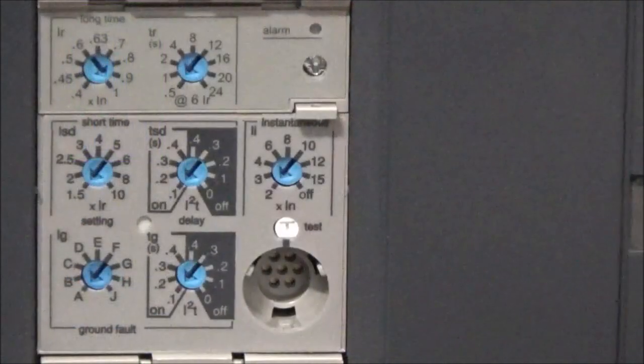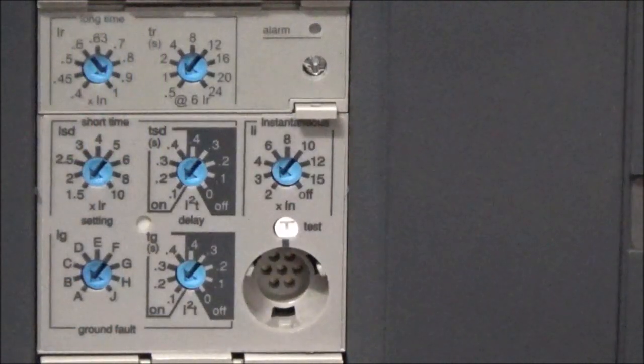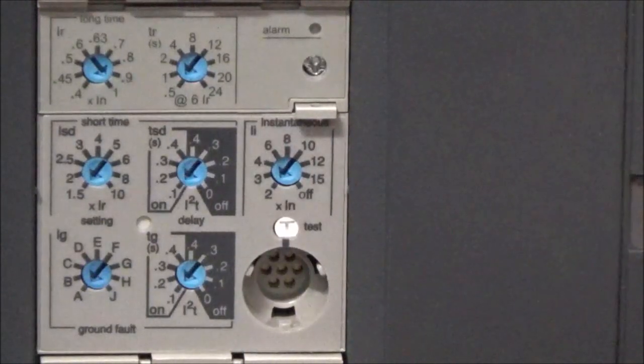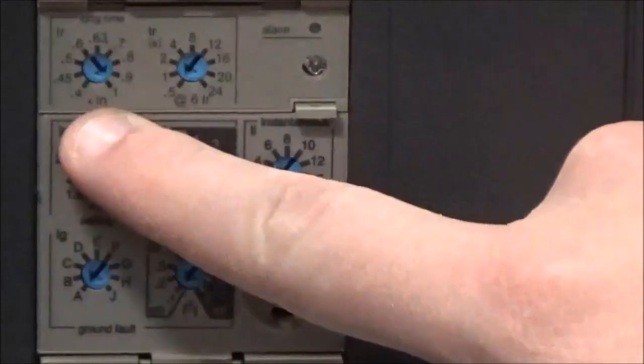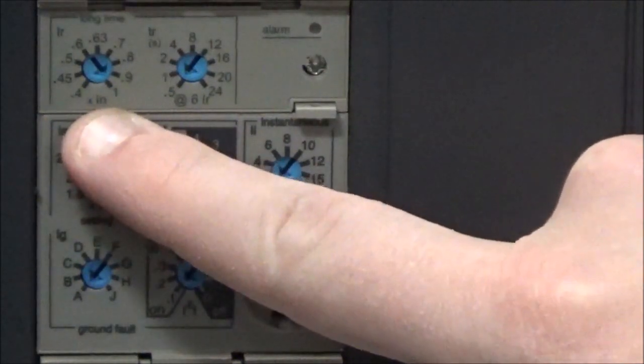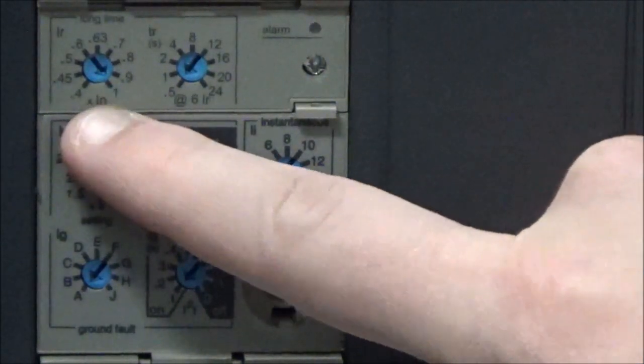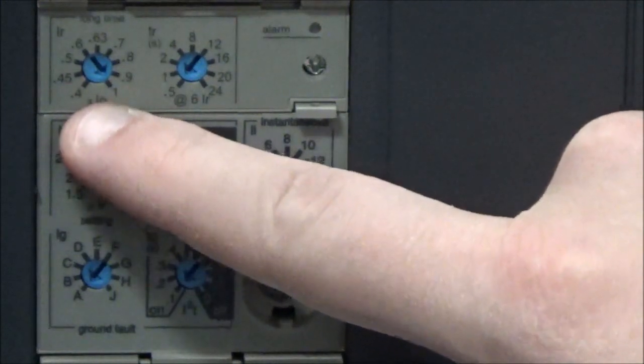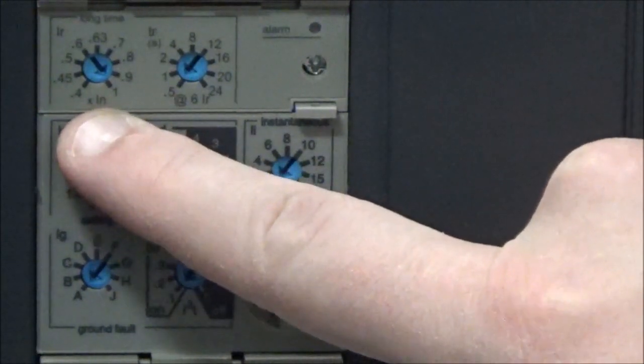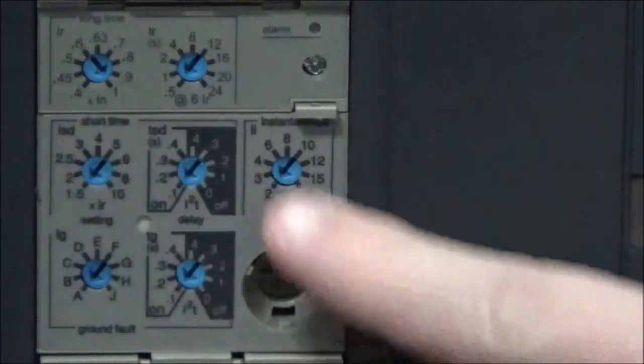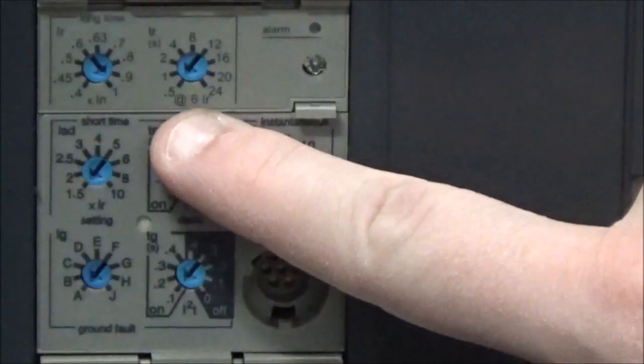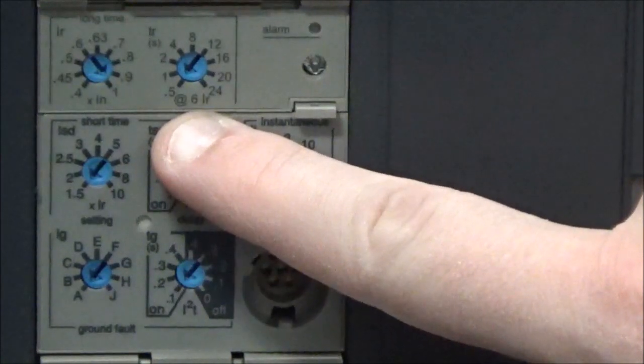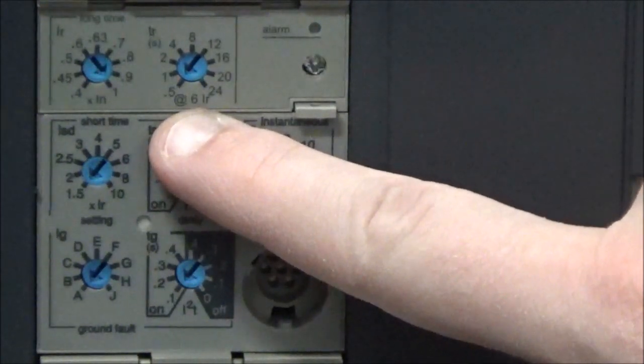The dials that are available on the MicroLogic 5.0 trip units will be the IR dial, which is the long time trip point. The settings that are on here are multipliers of the sensor rating of the breaker. You will also have the TR dial, which is the long time delay setting. All of the settings that are on this dial are given in seconds.